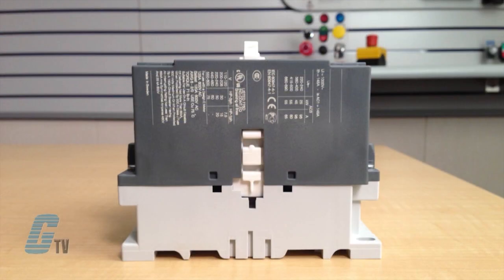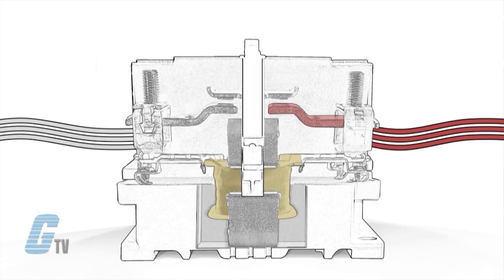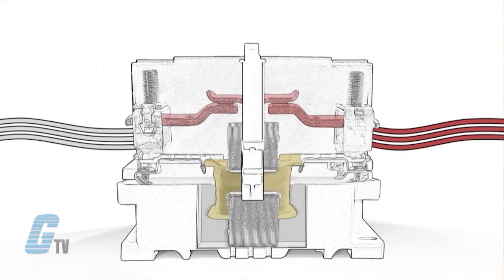Contactors operate when the E-frame is energized by the coil and becomes an electromagnet. The armature, a companion to the E-frame, is connected to a set of contacts. The armature is movable but is held by a spring. When the coil is energized, the movable contacts are pulled toward the stationary contacts because the armature is pulled toward the E-frame. Once the two sets of contacts meet, power can flow through the contactor to the load.